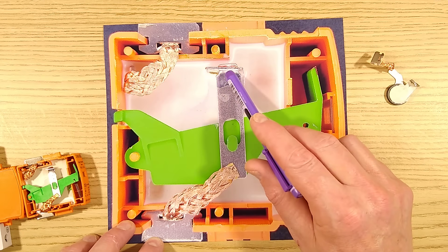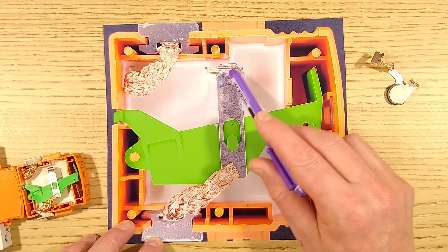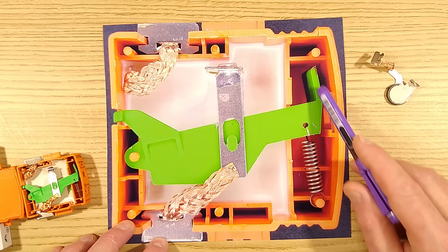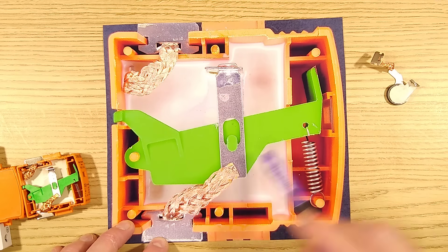With low-melting temperature solder on it, and a little spring-loaded pivot pulls down so that when that starts heating up, theoretically, it will melt the solder. And when it does, it breaks the circuit down to the other end, and also this little flag goes down to show that it's tripped.